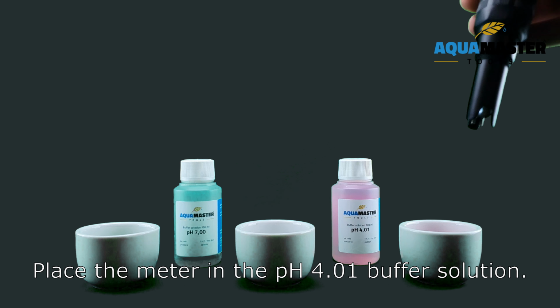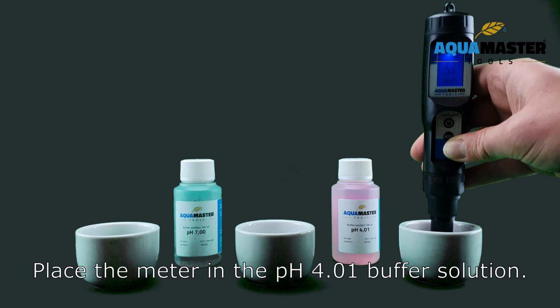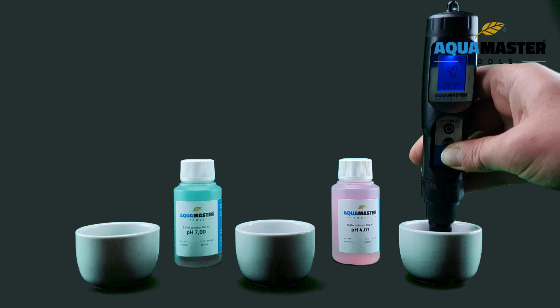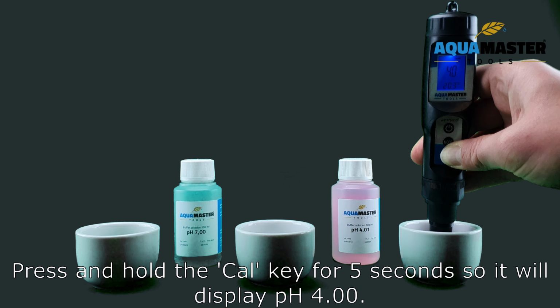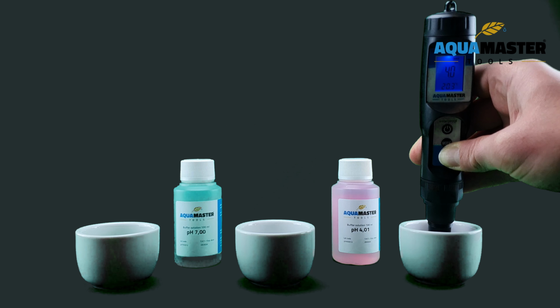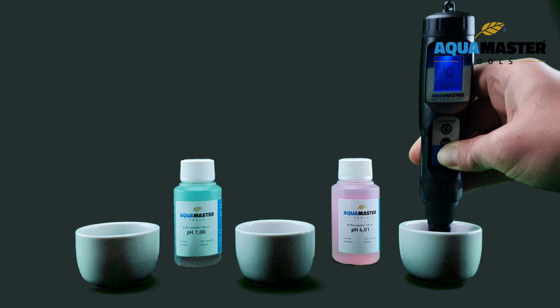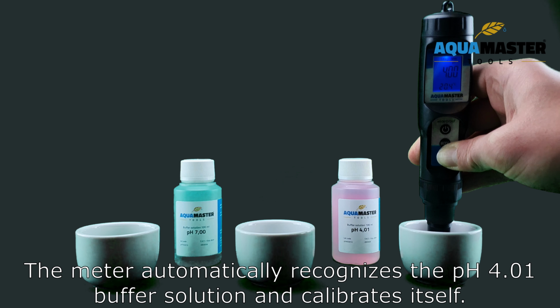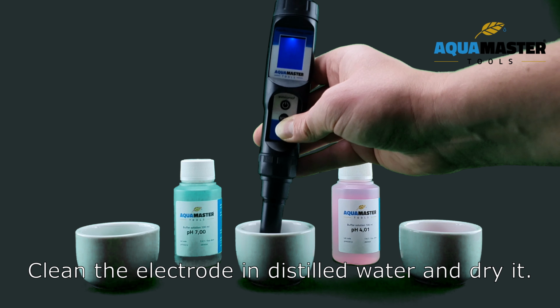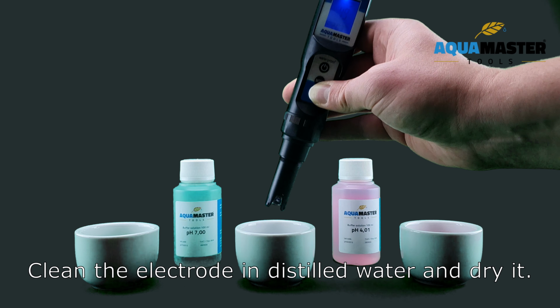Place the meter in the pH 4.01 buffer solution. Stir gently and wait for the value to stabilize. Press and hold the cal key for 5 seconds so it will display pH 4.00. The meter automatically recognizes the pH 4.01 buffer solution and calibrates itself. When the meter switches back to normal mode, the calibration is done. Clean the electrode in distilled water and dry it.